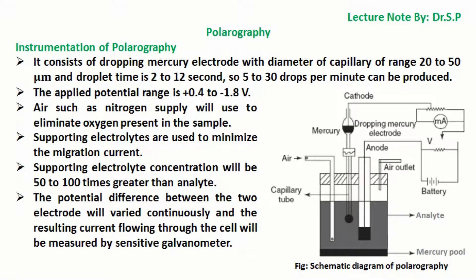Instrumentation of polarography consists of a dropping mercury electrode with a capillary diameter in the range of 20 to 50 micrometers, and droplet time is 2 to 12 seconds, so 5 to 30 drops per minute can be produced. The applied potential range is +0.4 to −1.8 volts. An inert gas such as nitrogen is used to eliminate oxygen present in the sample. Supporting electrolytes are used to minimize the migration current, and the supporting electrolyte concentration is 50 to 100 times greater than the analyte.